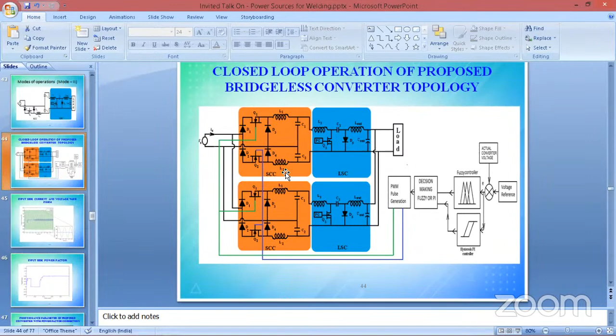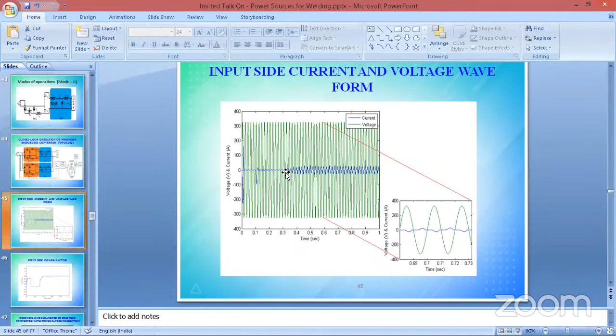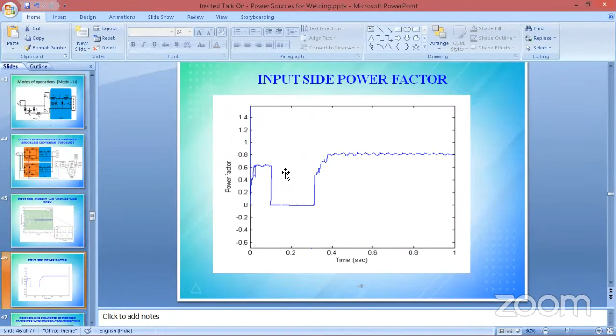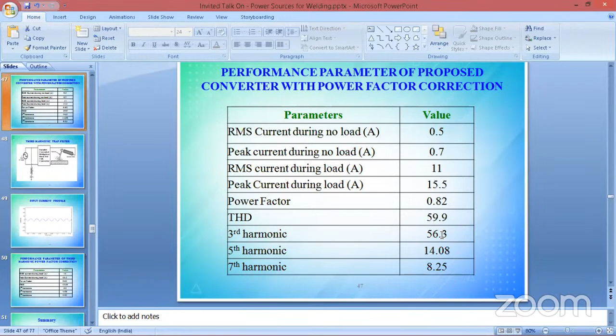Now when you see the graph, the current waveform issue is partly solved, not as drastically pulsating. The power factor moves to around 0.8 or 0.9, and the THD comes down to 59.9, mostly due to the third harmonic—we can clearly see around 56.3 is from the third harmonic.